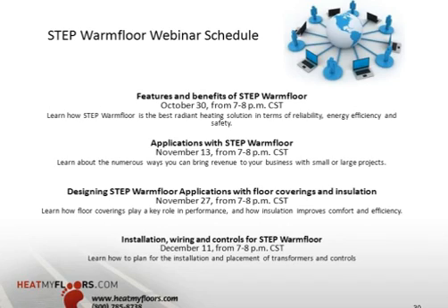So getting back, one of the questions I got was, can STEP Warmfloor be used to heat the entire house? And the answer is yes, absolutely. In fact, this can be the primary heat source for heating the home. The main thing we would need, as would you, is information so we can calculate a heat loss on the structure, so we can effectively design a system that is going to meet the heating degree days of the location where you live.